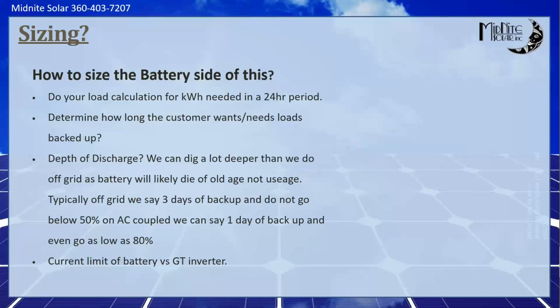So again, do your load calculations for a 24-hour period, figure out how much they want to back up. If they only want 12 hours, you divide it by 2 and add a little for your cushion. If you're using lithium, you can be down to the 20% state of charge easy. If you're using lead, maybe stay around 25 if it's a backup. And again, if it's off grid, we typically say 3 days of backup and try not to go below 50% on a lead acid battery.